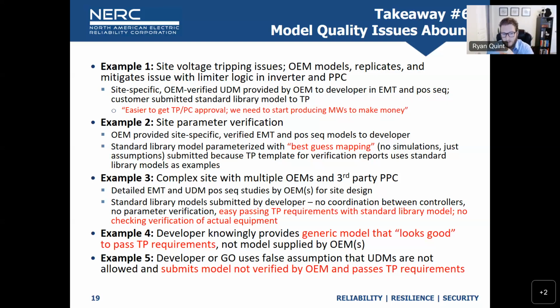Example 3: a complex site with multiple OEMs and a third-party PPC—not uncommon in today's interconnections. A detailed EMT and detailed UDM for positive sequence were provided by the OEM matching the site design. Yet again, a standard library model was submitted with no coordination between controllers and no parameter verification. It comes down to this: it's super easy to pass TP requirements using a standard library model, and you don't need to verify actual equipment settings. So why bother with the detailed UDM model?